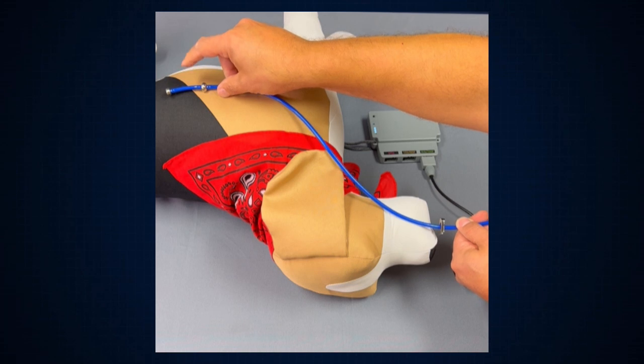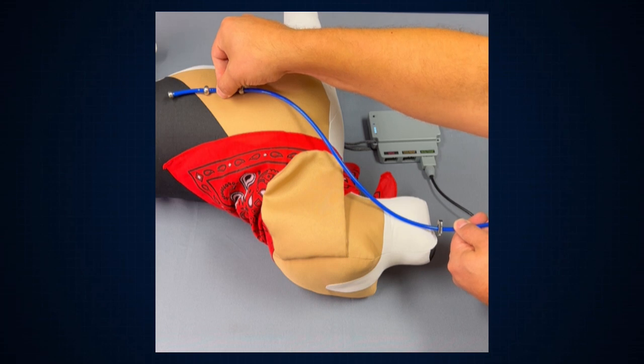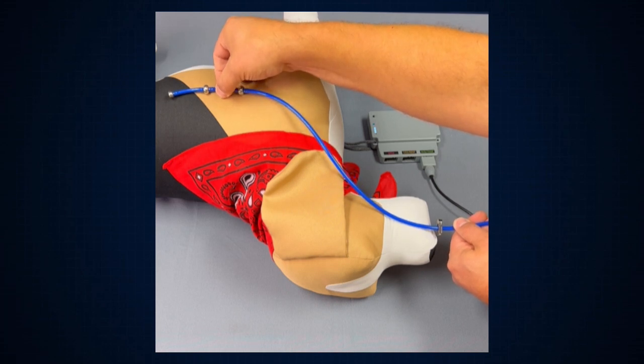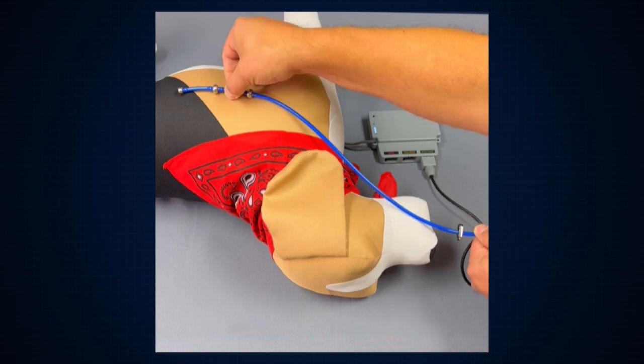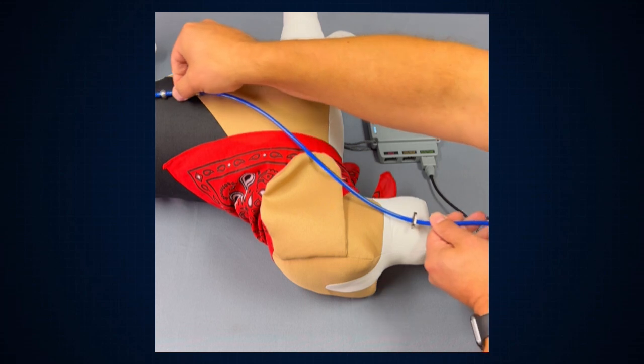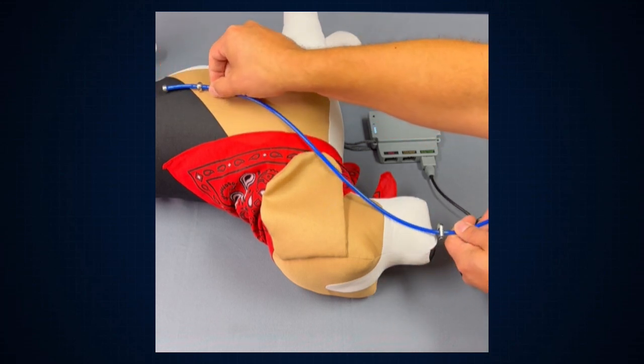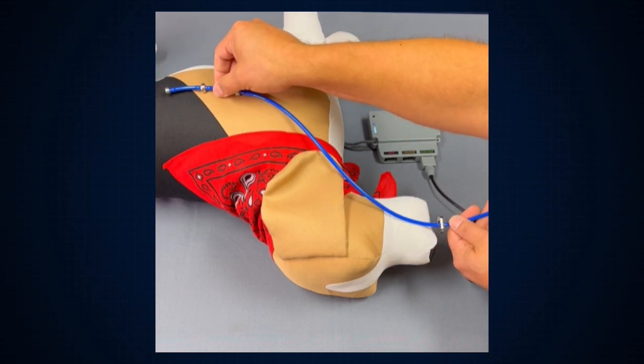What that does is it relubricates the contact points by the natural moisture in the esophagus, and relubricating those contact points will advance or increase the quality of the conduction, and that will give you much better ECGs as well. Of course, if the probe were to pull out or go further in during a procedure, just again use your pre-measured marked location as your guide, and you'll be good to go.